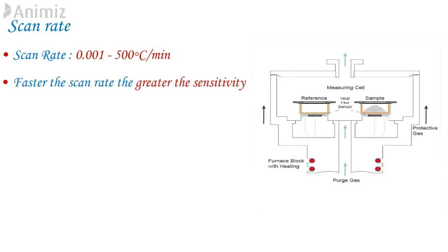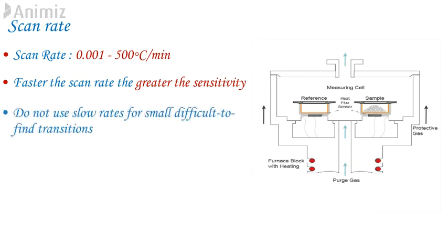1. Sensitivity. Faster the scan rate, greater the sensitivity. The reason for this is that DSC measures flow of energy and during a fast scan the flow of energy increases though over a shorter time period. A slow scan rate means lower flow of energy over a longer time period. But since DSC data are usually shown with X axis as temperature, it simply looks like the transition is bigger at a faster rate. Hence, an increased scan rate leads to increased sensitivity. So, do not use slow rate for small difficult to find transitions unless otherwise unavoidable.